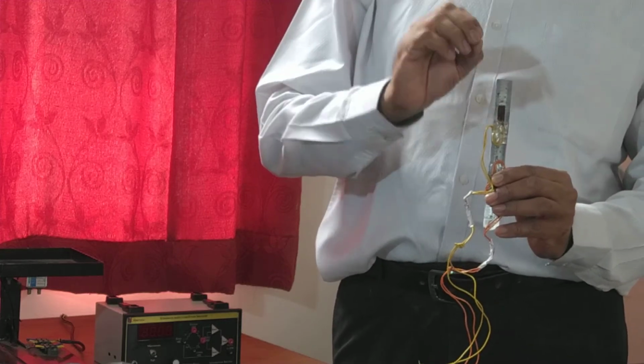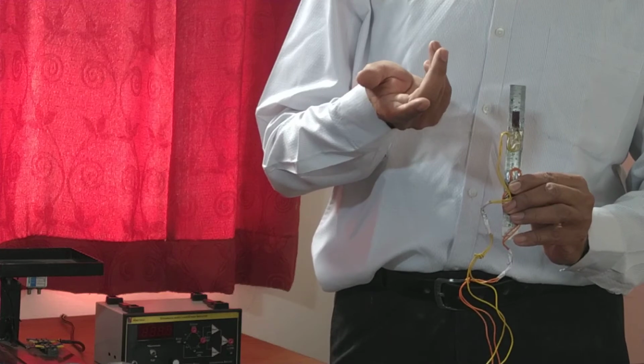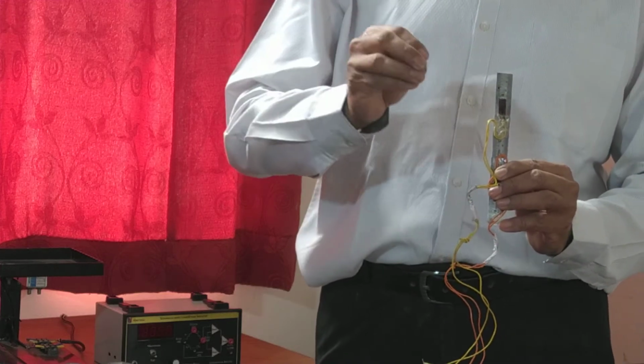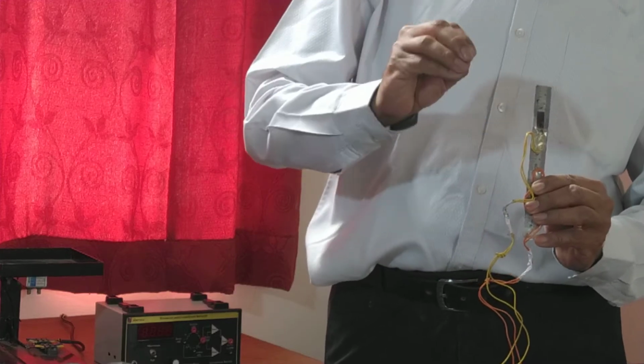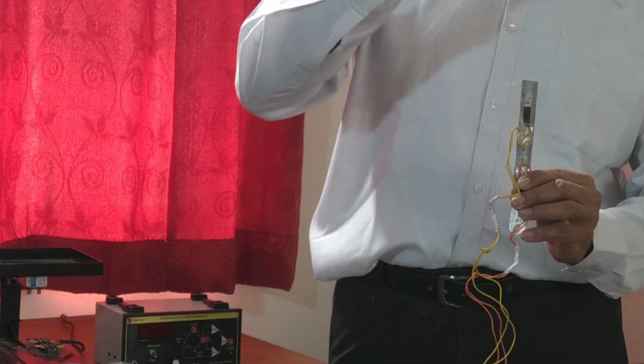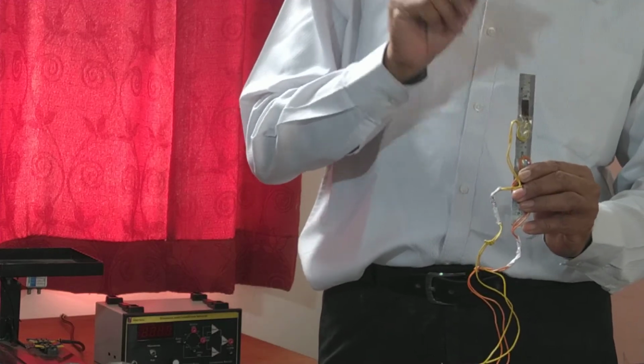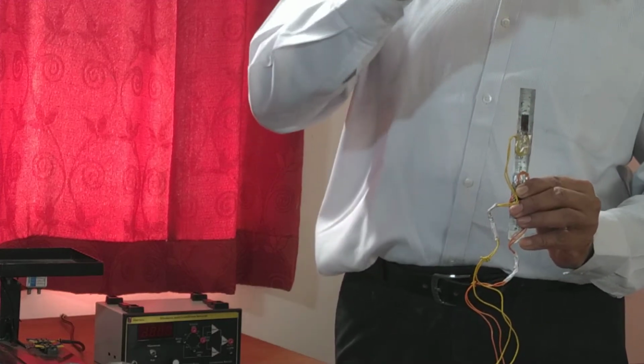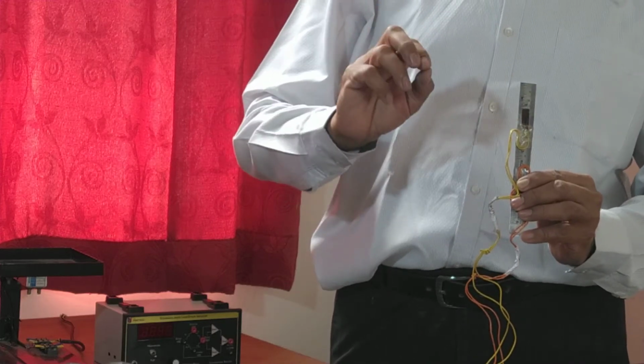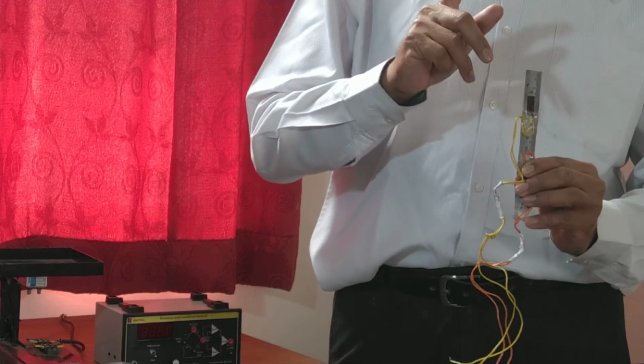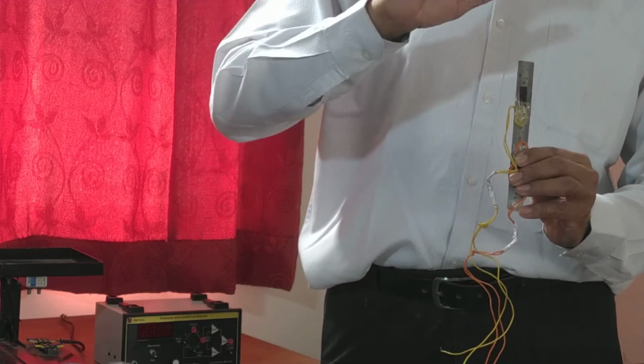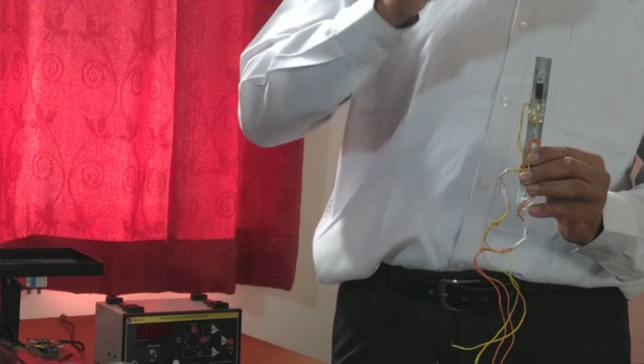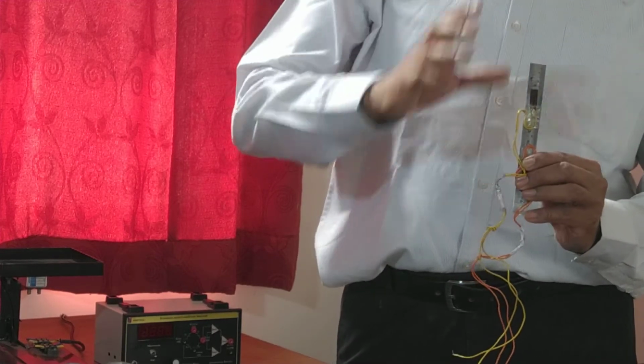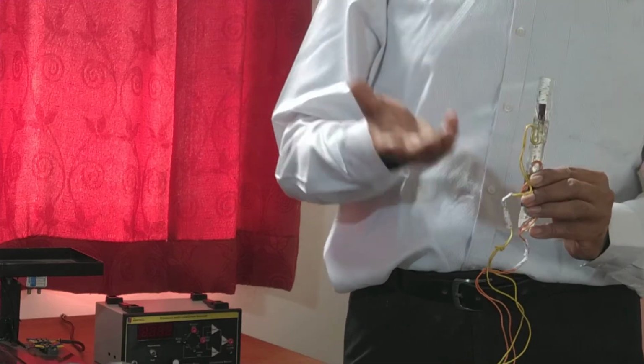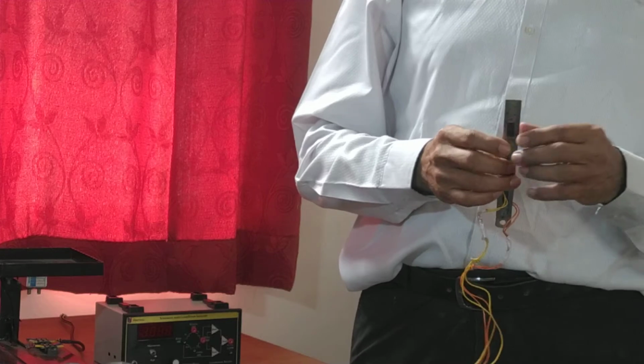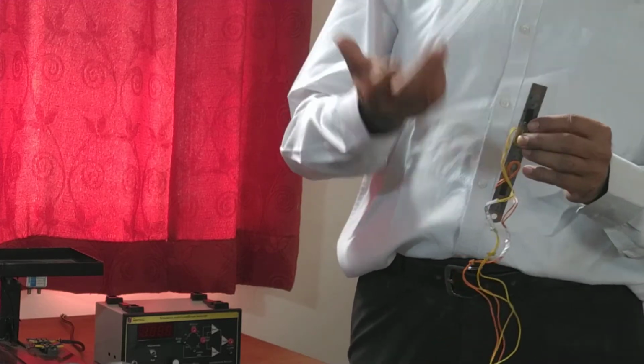The value of K, the gauge factor, provides the sensitivity factor. Corresponding to unit change in length, or unit change in strain, how much resistance change I am obtaining. So if the gauge factor is 2, the resistance change corresponding to unit change in length or strain is double. Higher the gauge factor, higher will be the sensitivity of the strain gauge, or in simple words, higher the gauge factor, higher the amplifying factor. So I should try to use a strain gauge with higher sensitivity or higher gauge factor.